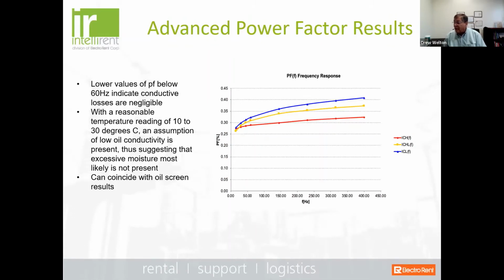So what we see here, and you'll see your three typical power factor measurements, is that the lower values of power factor indicate that conductive losses are negligible. In other words, if you had a moisture issue, you would not see these types of results. With a reasonable temperature reading of, let's say, 10 to 30 degrees C and an assumption of low oil conductivity, that suggests that excessive moisture in all instances probably isn't there. And if that coincides with your oil screen results, you can be pretty confident that you don't have a moisture issue in the transformer itself.